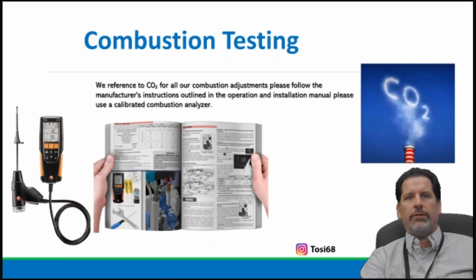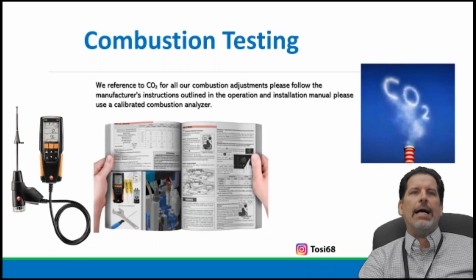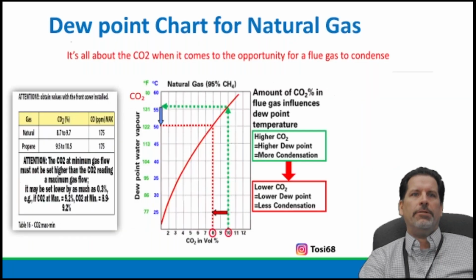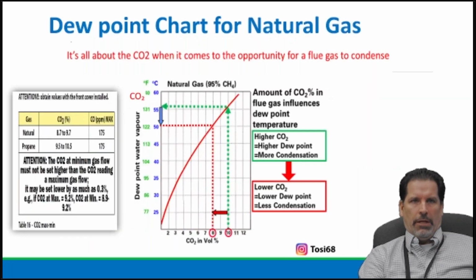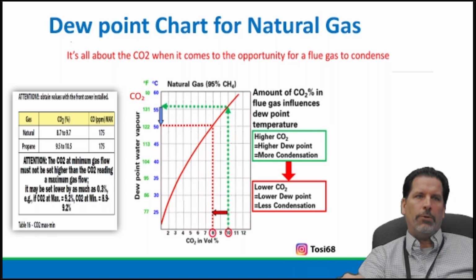Using tools like a combustion analyzer, we have the ability to do what? Dial in our combustion, right? When we dial in our combustion and we set our gas valve and we achieve certain CO2s by lowering water temperature, that's when we're going to achieve that high efficiency. This chart, if I can show you really quickly, on the left is a manufacturer's specification, what they're asking us to do with our combustion analyzer.